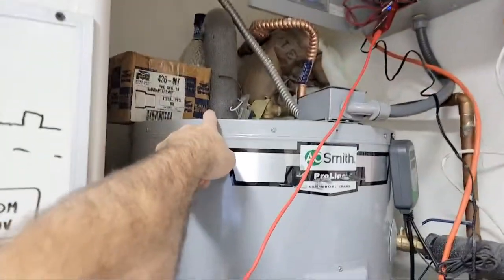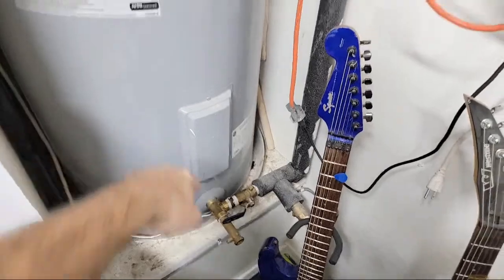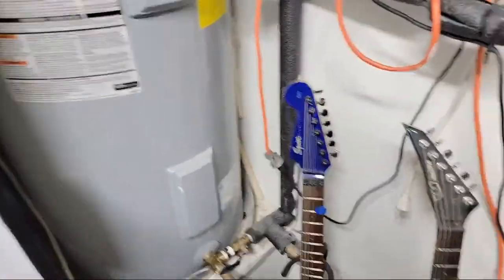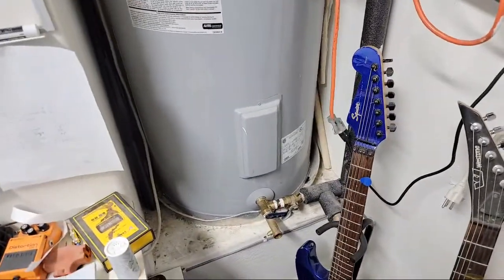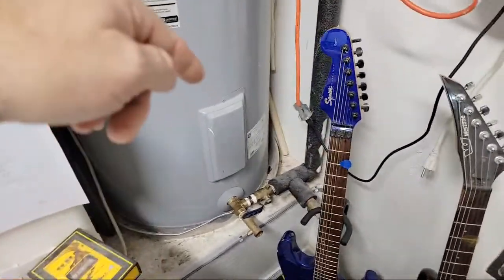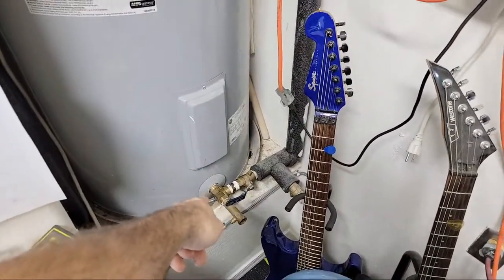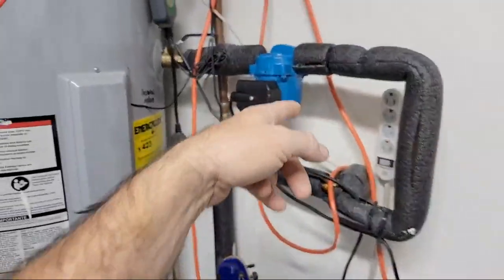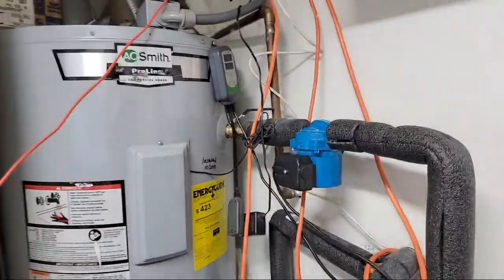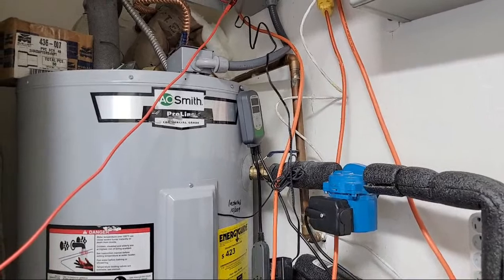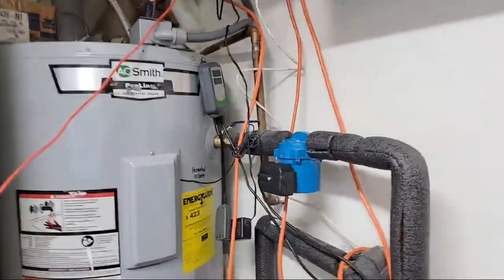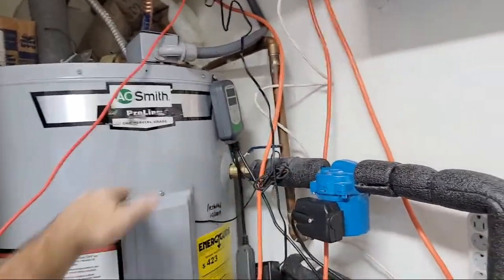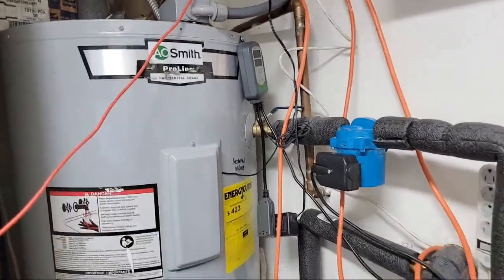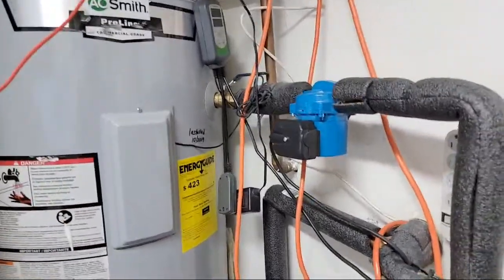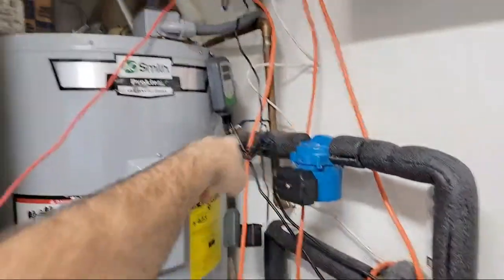When you're taking hot water right over here, your cold goes through a dip tube in water heaters, and they put the cold down there. Well, interesting thing, especially when it's cold and our groundwater gets into the 40s and 50s, is that really cold water shoots right there, through a heat exchanger. And if the performance of the compressor at the moment wasn't all that great, it seemed like it actually initially dropped a little bit of the temperature of the water in here when it was basically mixing it up, but it wasn't adding much heat to that cold at first.